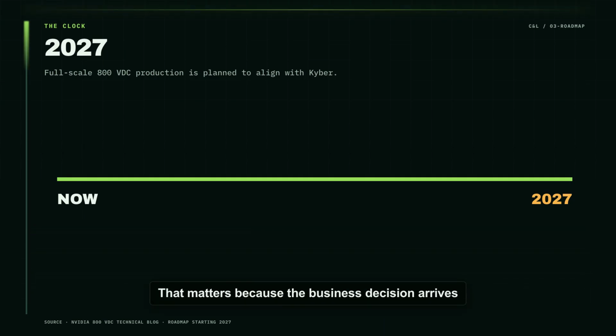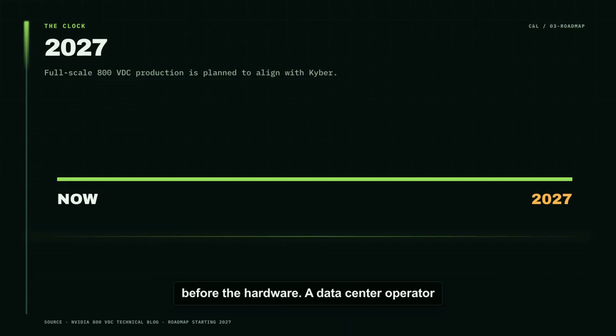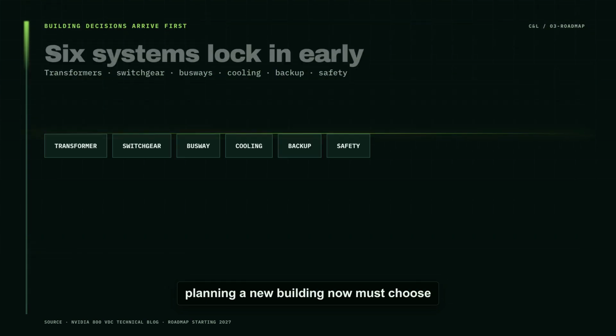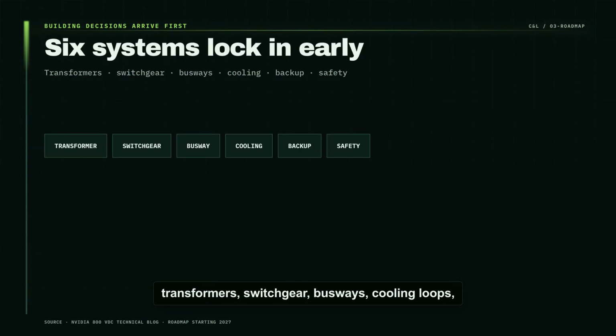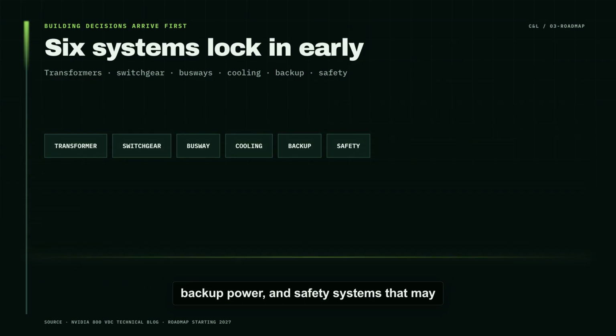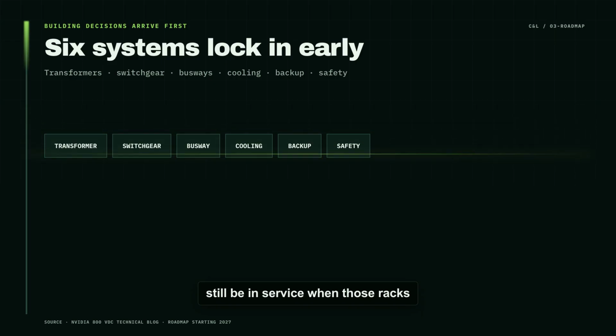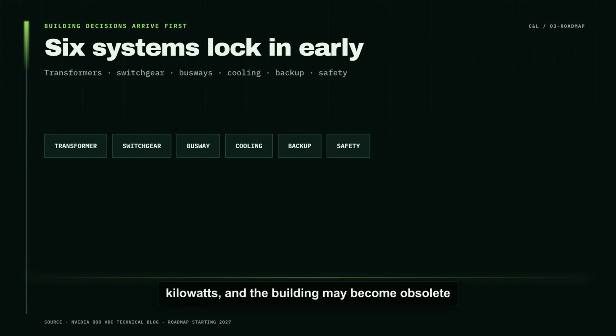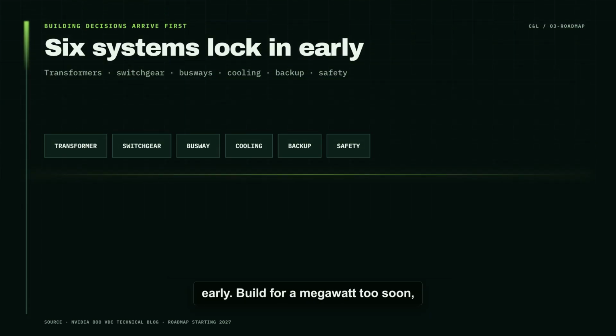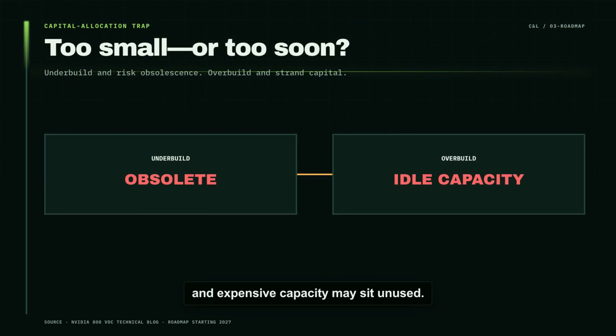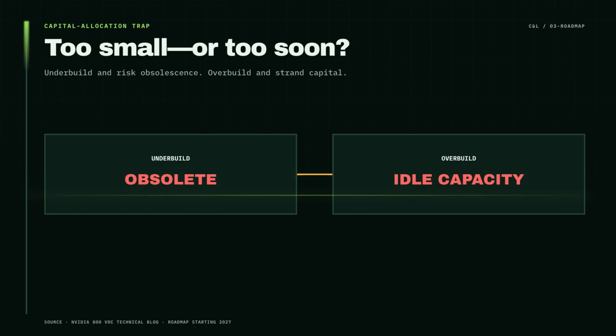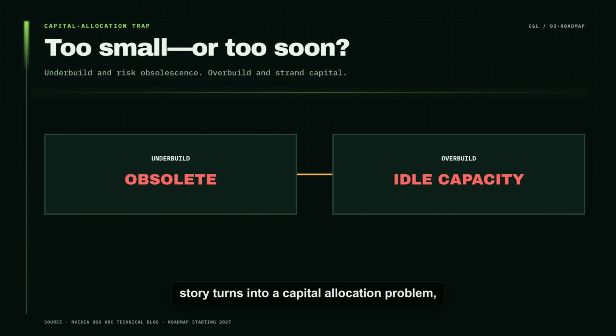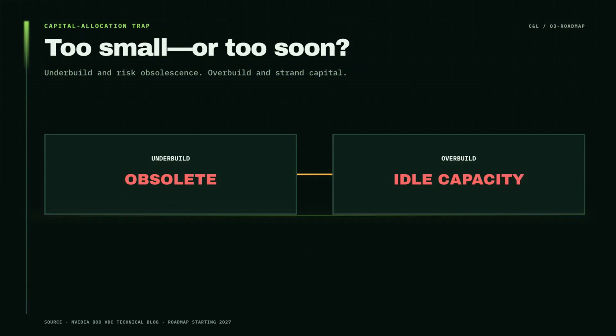That matters because the business decision arrives before the hardware. A data center operator planning a new building now must choose transformers, switchgear, busways, cooling loops, backup power, and safety systems that may still be in service when those racks arrive. Build for today's 142 kilowatts, and the building may become obsolete early. Build for a megawatt too soon, and expensive capacity may sit unused. That timing gap is where the technology story turns into a capital allocation problem, and the hardest choice begins with a voltage that sounds almost mundane.